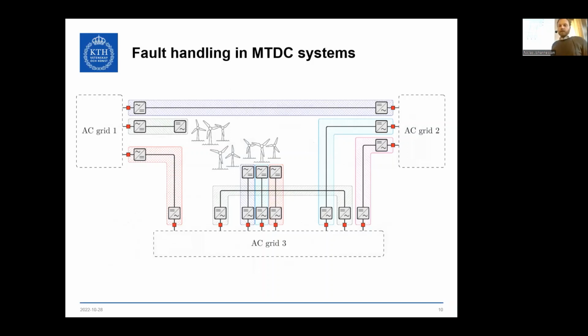This picture shows how to handle faults in point-to-point networks. When you have only 2 converters, in case you get a fault, you trip both of them, and then you can use the AC breaker on the AC side.